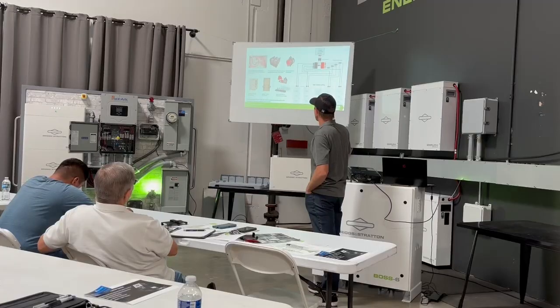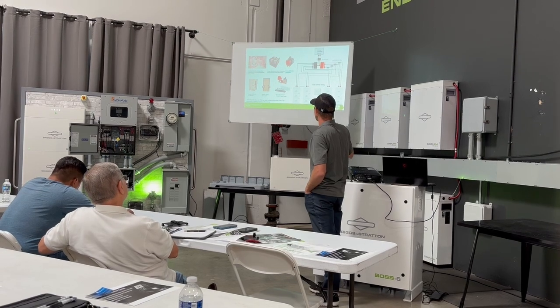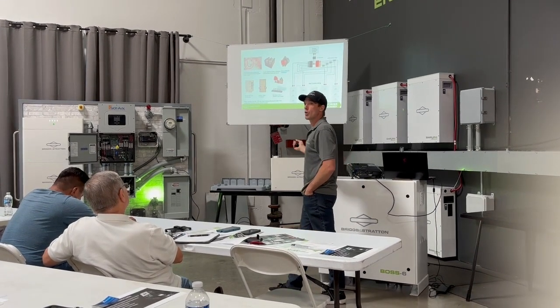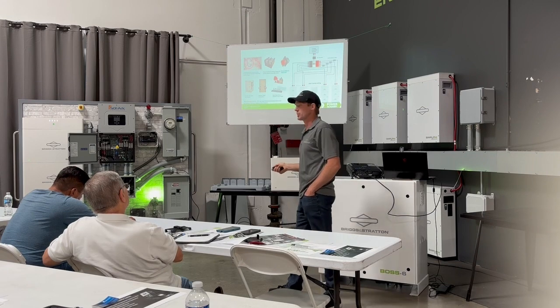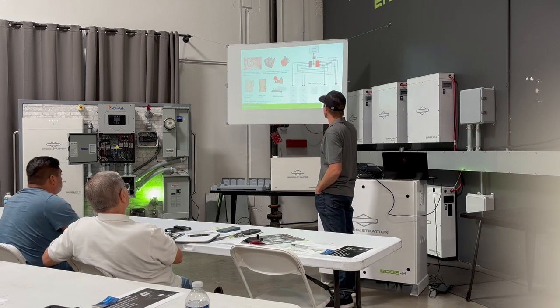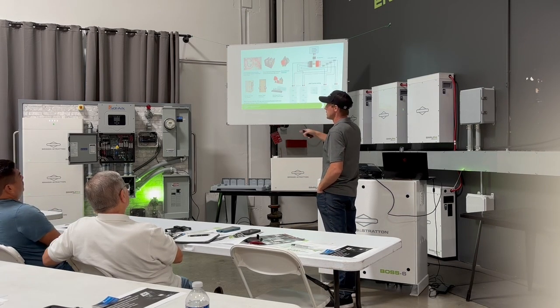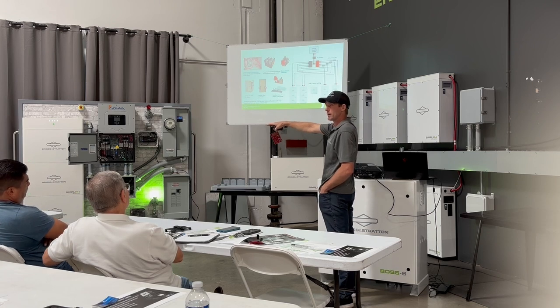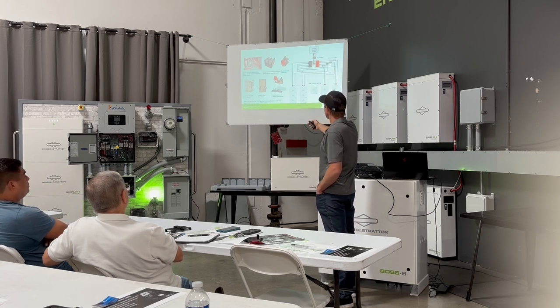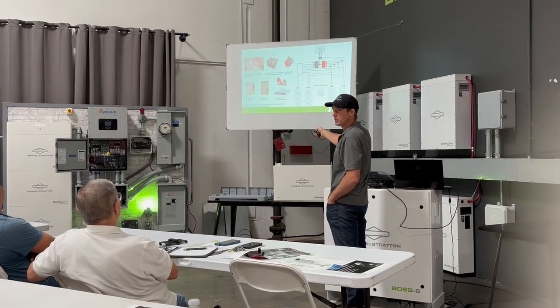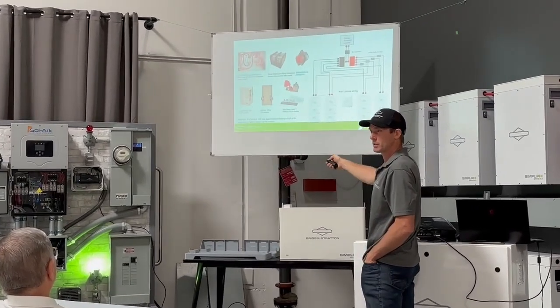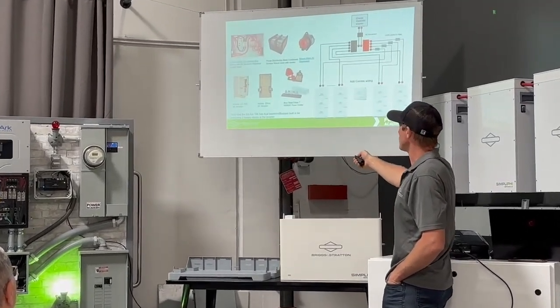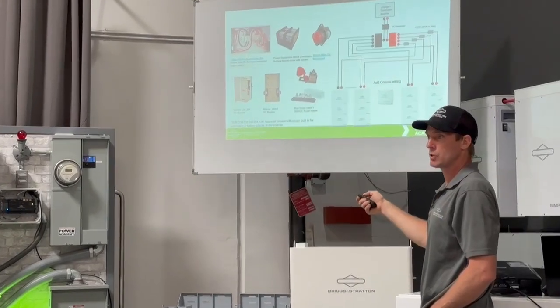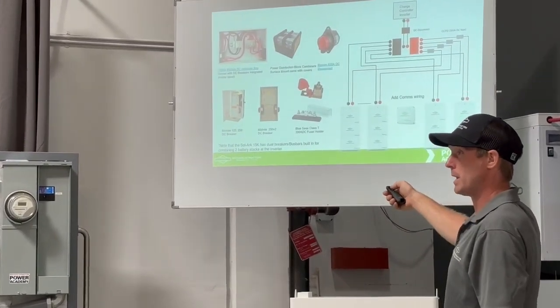Drawing from the whole bank, I'm not drawing too much current out of an individual stack, and that's why we require overcurrent protection. The Sol-Ark 15K has dual 200 amp breakers, but you can buy breakers on the side of this 1000 amp combiner—they don't come with it. The combiner itself is about $600, and the individual breakers are about $100 each. I'll show you a cheaper option in a minute.